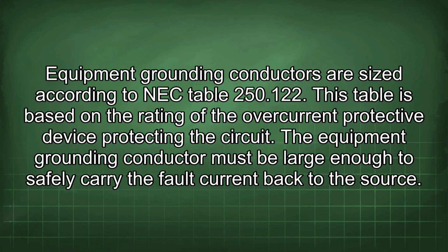Equipment grounding conductors are sized according to NEC Table 250.122. This table is based on the rating of the overcurrent protective device protecting the circuit. The equipment grounding conductor must be large enough to safely carry the fault current back to the source.